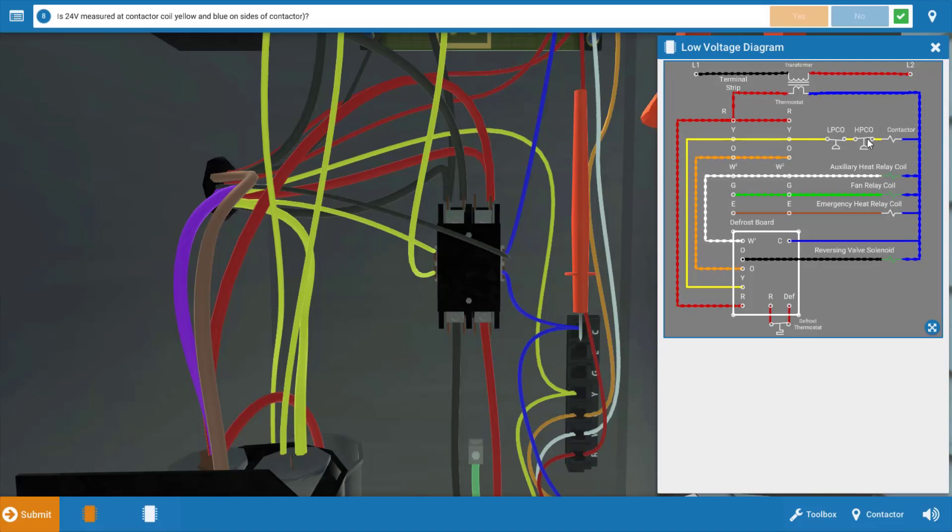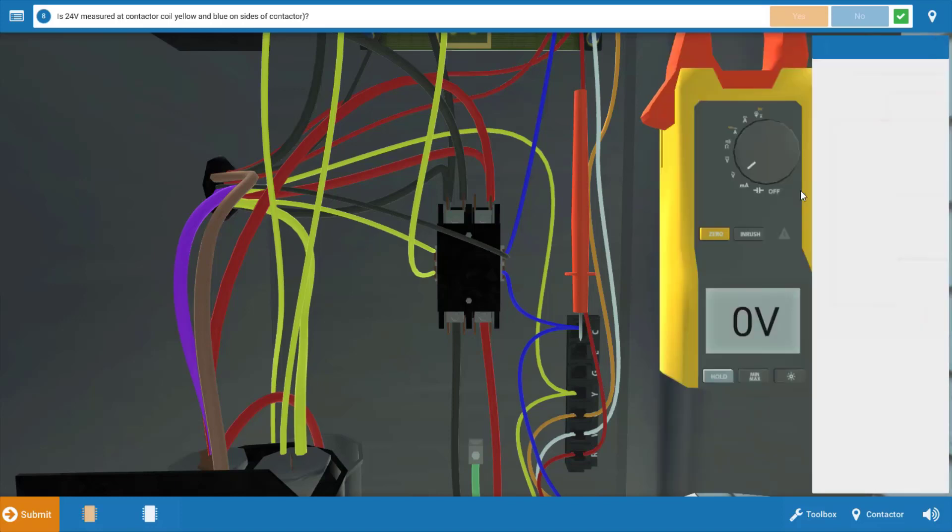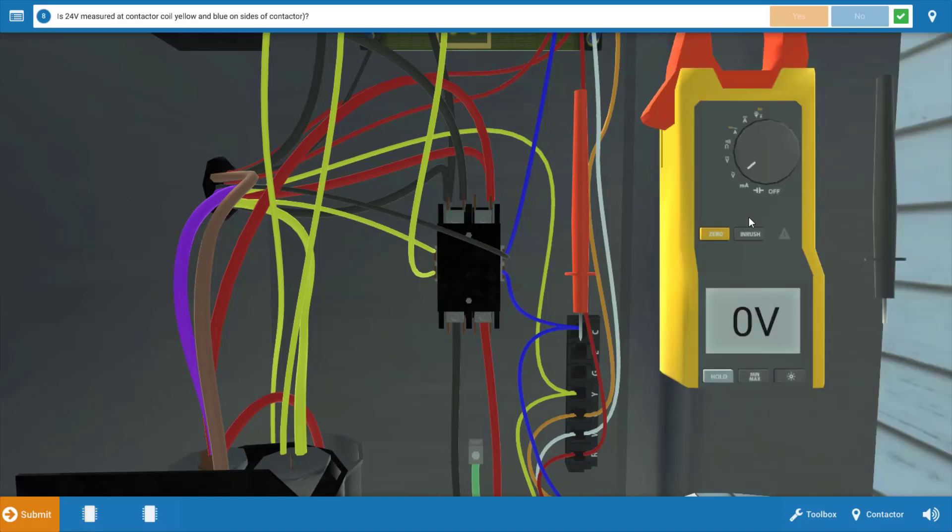So we're armed with basically four possible causes here: the contactor, the high pressure cutout, the low pressure cutout, or the thermostat. So now let's take some voltage readings and find out which of these it is.